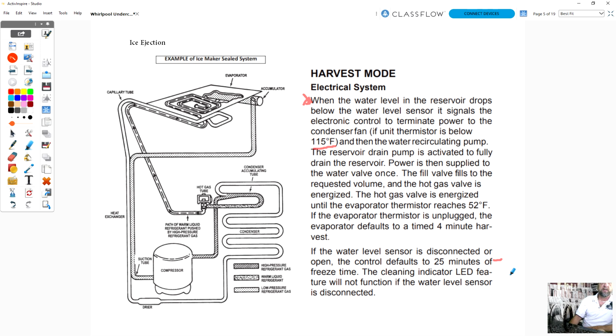Well, they use the water level sensor. If the water gets down to a certain level, it's assumed, okay, well, now that all that water is gone, it's got to be ice up in the slab. Let's go ahead and drop the ice. So instead of using a thermistor on the suction line, they're using a water level sensor, and I'll point them out to you as we go through the slides. So this is one of the main changes that they did on the newer unit. They've added a drain valve. They've added a water level sensor to the system and changed the way it's cycled.